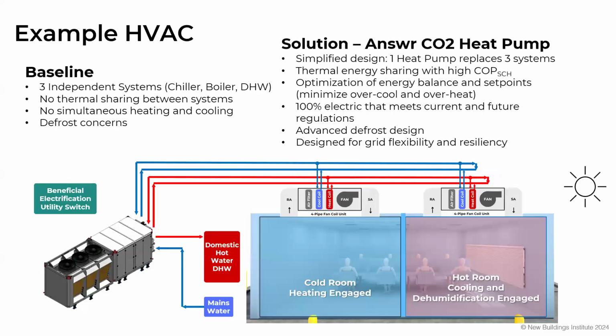So this is our HVAC unit. I'll share this briefly and then turn it over to look at some details. This is what is in the new Title 24 California Energy Codes, and a lot of people are switching to hydronics with chilled water, hot water, fan coils, air handlers, etc. But the main takeaway is one system can do 3 independent operations, 3 capacities, 1 power feed. That allows us to really simplify the mechanical infrastructure of the system and optimize energy sharing. So instead of having a COP of, let's say, 3 or 4, you can optimize that to a COP of 7 or 8 and combine those loads together like before. With some of the advanced defrost designs, we can have an always-on active defrost with no performance derate - meaning we never have frost on the coils - plus some other great grid flexibility benefits. It's really a fantastic project.